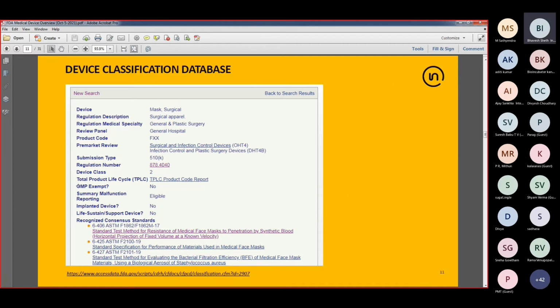The next key piece of information is about GMP exemption. As it says here, there is no exemption, which means manufacturers of surgical masks will need to comply with good manufacturing practices, basically the quality system regulations. And the applicable standard for quality systems, medical device quality management systems, is ISO 13485. So this is some key information you can find right away from the device classification page.